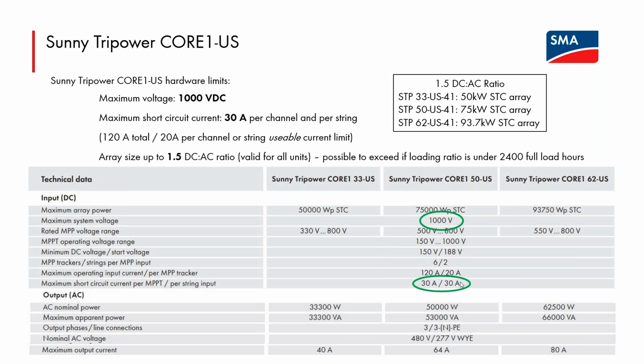The spec sheet information, we're showing the top of the spec sheet for the 3 power classes of the CORE1 US-41 line here on the lower part of this slide. Kind of boring, apologies for all of this technical information. The 2 values circled in green are the limits for the inverter that SMA cares about. This is a 1000 volt rated machine, so none of the inputs on any of those 6 input channels to the inverter, at the coldest temperature the system's exposed to, should ever exceed 1000 volts. So again, that is the limit for each and every input and all of the channels on the inverter.